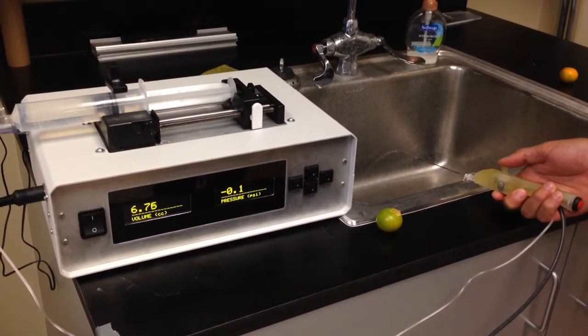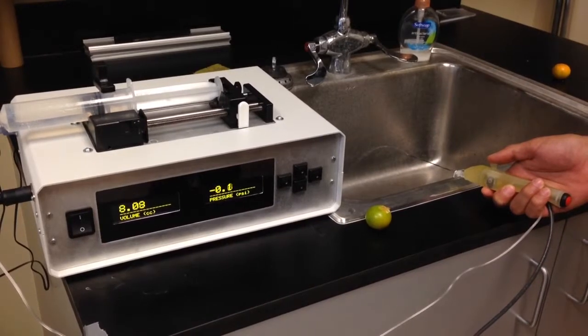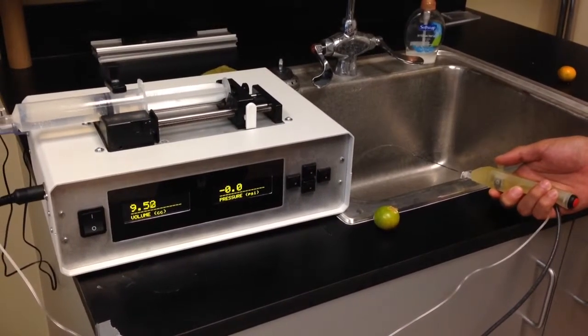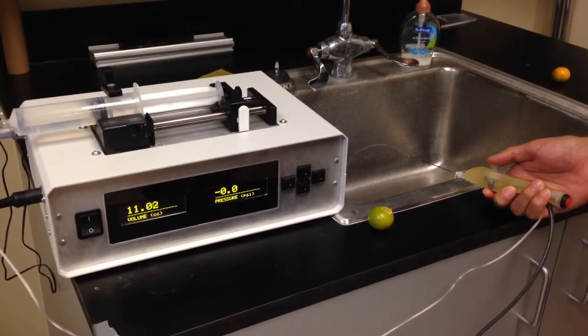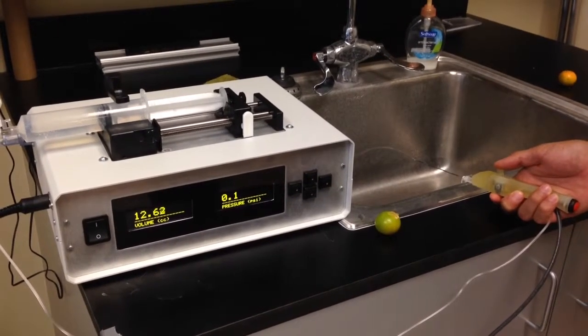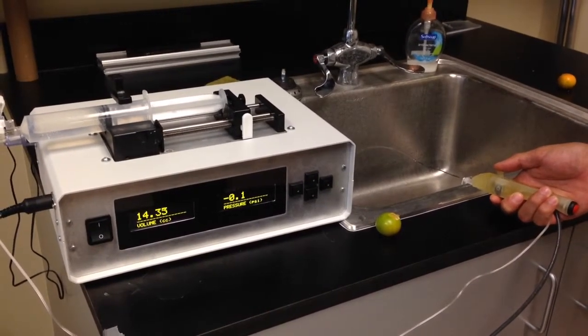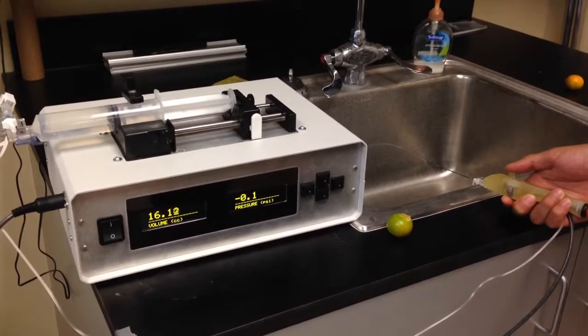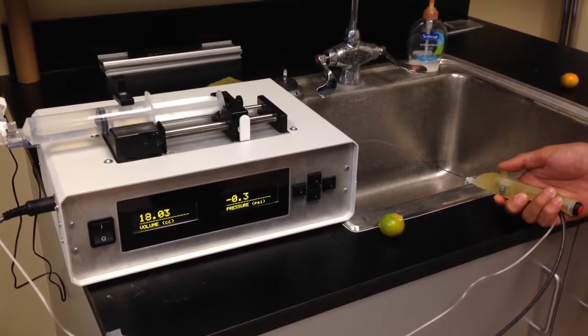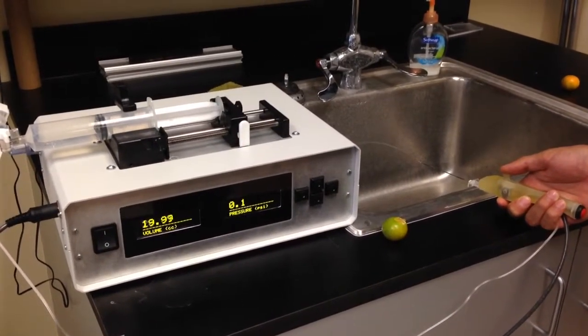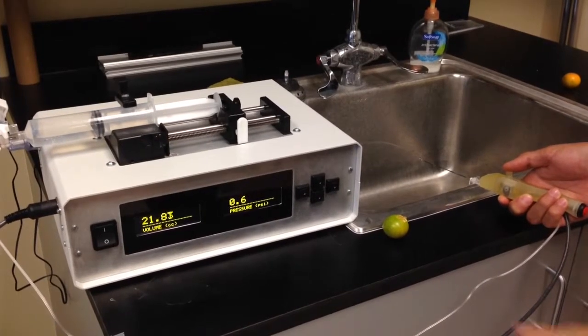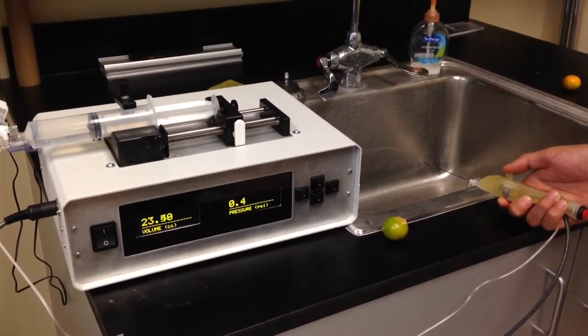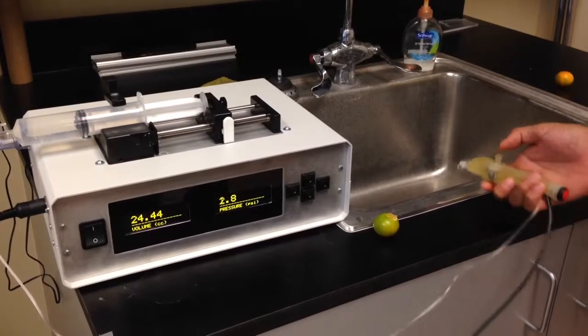The maximum flow rate is 1 cc per second infusion. You can see on the left the volume being dispensed and the pressure on the right. Rene will now inject into this fruit to show you the difference in the pressure readings when you're injecting into atmosphere and when you're injecting into a closed body.